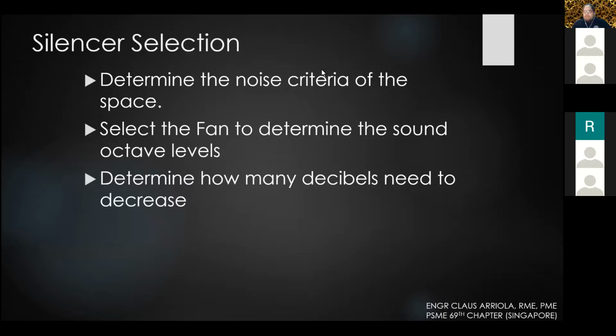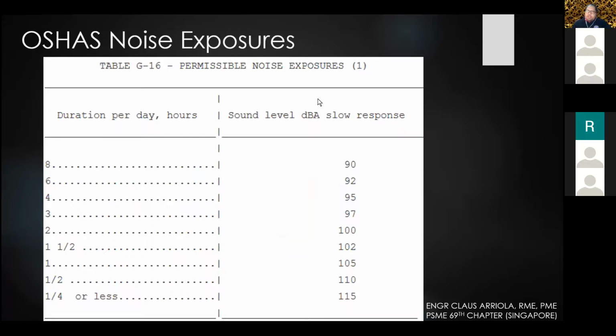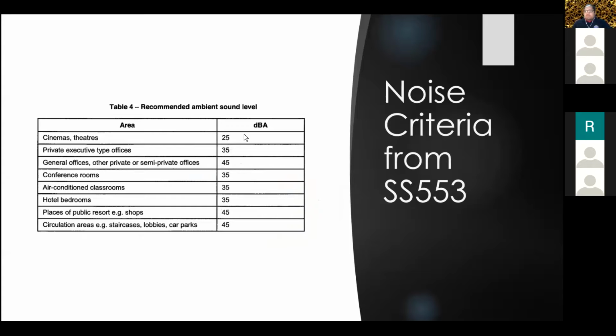This noise criteria might not be based on OSHA or the recommended sound level, but you need to notify the client: are you agreeable with, let's say, 50? Are you agreeable with 55? Then you need to have an email record that you agreed with 55, and I will design it based on 55. It is also not recommendable to design for 45 or maybe 35 decibels if you're just testing 3 times a year, right? So you need to meet halfway with the client.